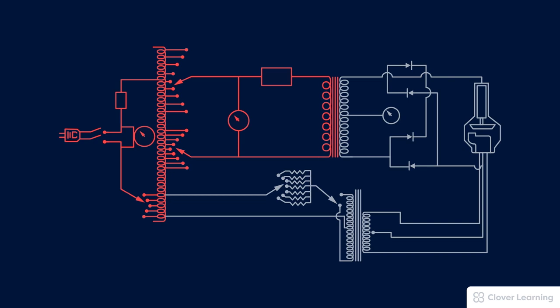When the technologist sets the kilovoltage potential, that's the kVP, this change occurs in the circuit through a device called an auto transformer. Without the auto transformer, we wouldn't be able to change the kVP to different settings.